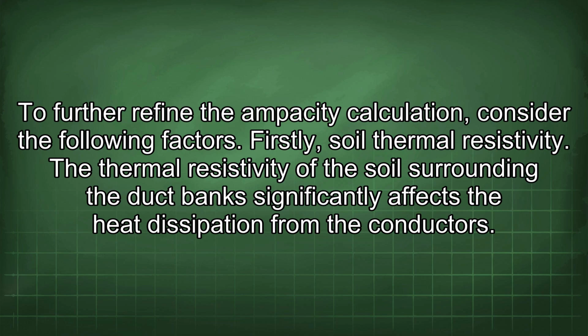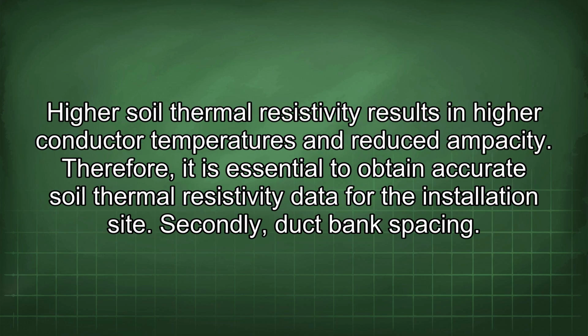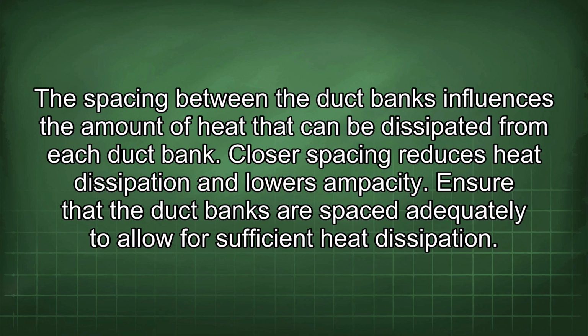Firstly, soil thermal resistivity. The thermal resistivity of the soil surrounding the duct bank significantly affects the heat dissipation from the conductors. Higher soil thermal resistivity results in higher conductor temperatures and reduced ampacity. Therefore, it is essential to obtain accurate soil thermal resistivity data for the installation site. Secondly, duct bank spacing. The spacing between the duct banks influences the amount of heat that can be dissipated from each duct bank. Closer spacing reduces heat dissipation and lowers ampacity. Ensure that the duct banks are spaced adequately to allow for sufficient heat dissipation.